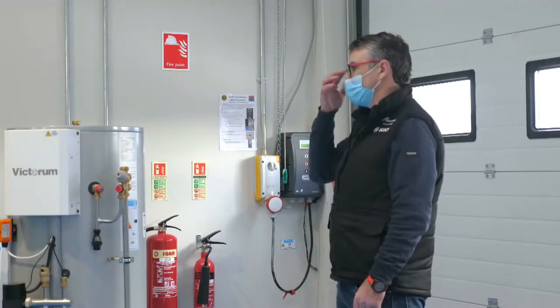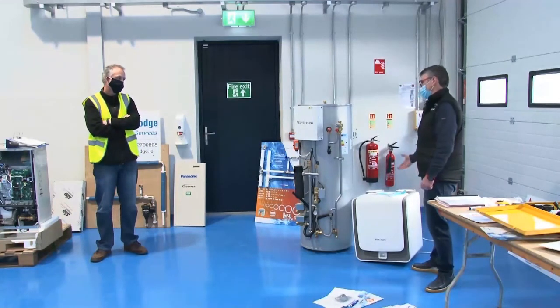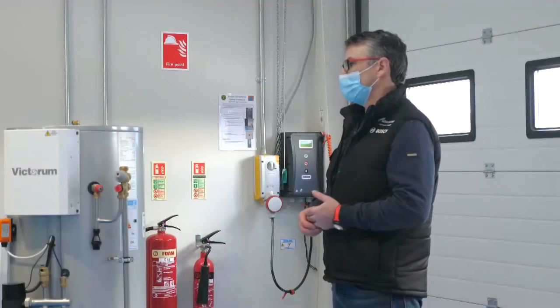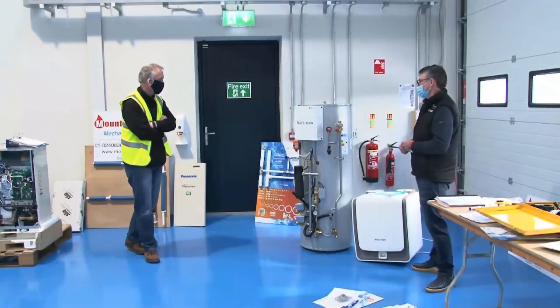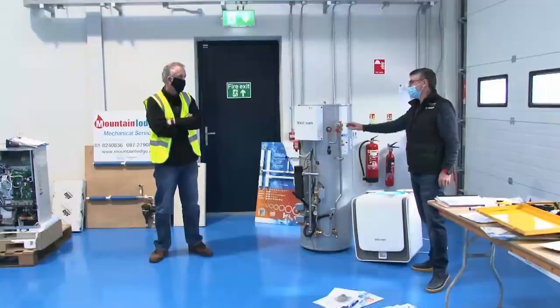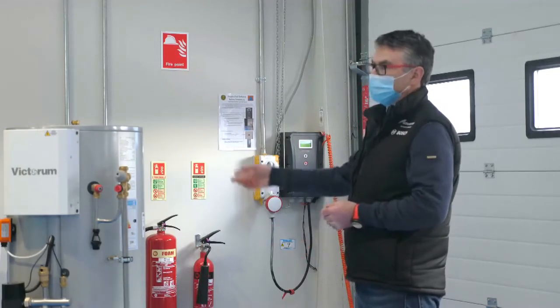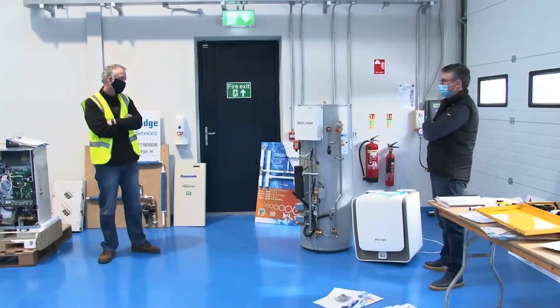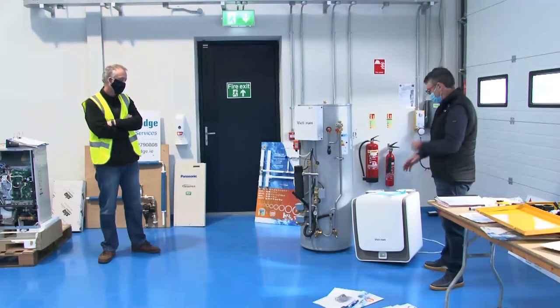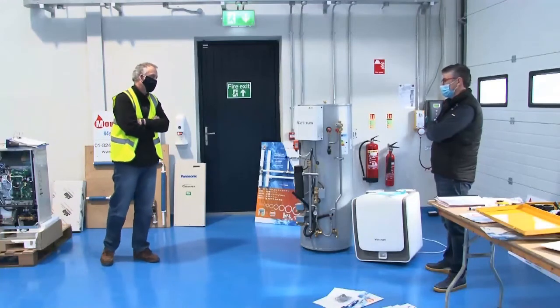But again, it's going to be for maintenance. It's going to be somebody that needs to know the workings of the unit to check it out. Generally, is it the installer then that would be doing it, if it's penetrating fire compartmentation? That will have to be worked out on site with the fire stop. Again, with the duct routes, you try and keep them out of the corridor, which is the main fire compartment. So you try and sort your duct routes so there are fewer penetrations and less interaction with any fire breaks. But the ducts can have purpose-built dampers. They're like any other penetration. Yeah, they have to be dealt with.